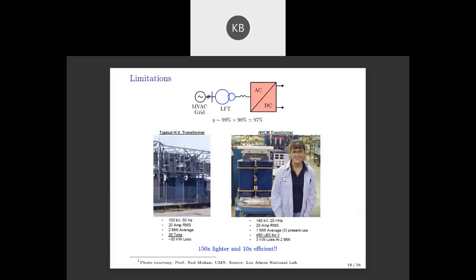So you increase the frequency from 60 hertz to 20 kilohertz, and the weight of the transformer got reduced by 150 times, because you now have a low amount of copper and iron. Your eddy current and copper loss also reduce, and the efficiency found in this case was increased. This is taken from a report from Los Alamos Lab, and I got this from Professor Mohan, University of Minnesota.